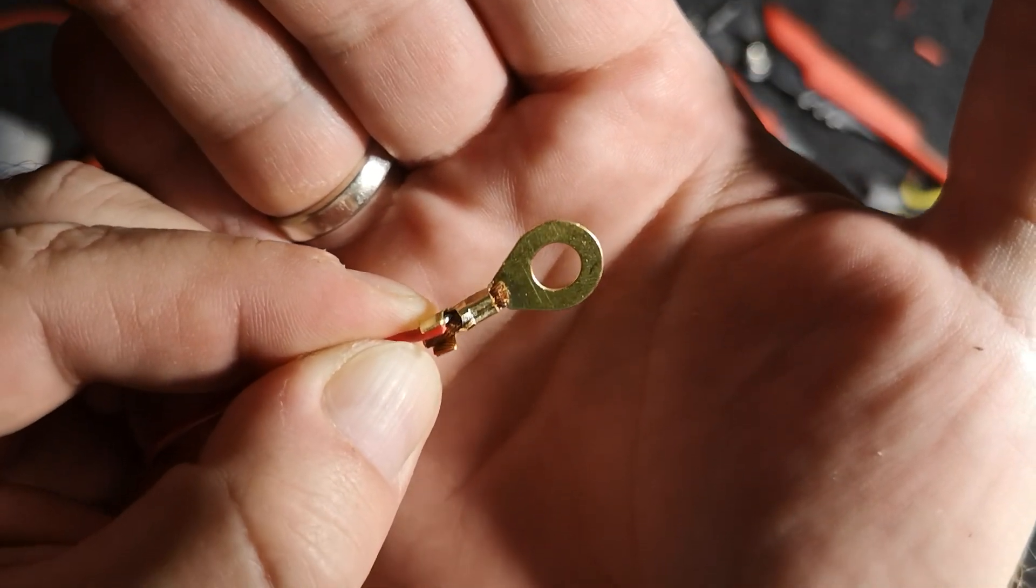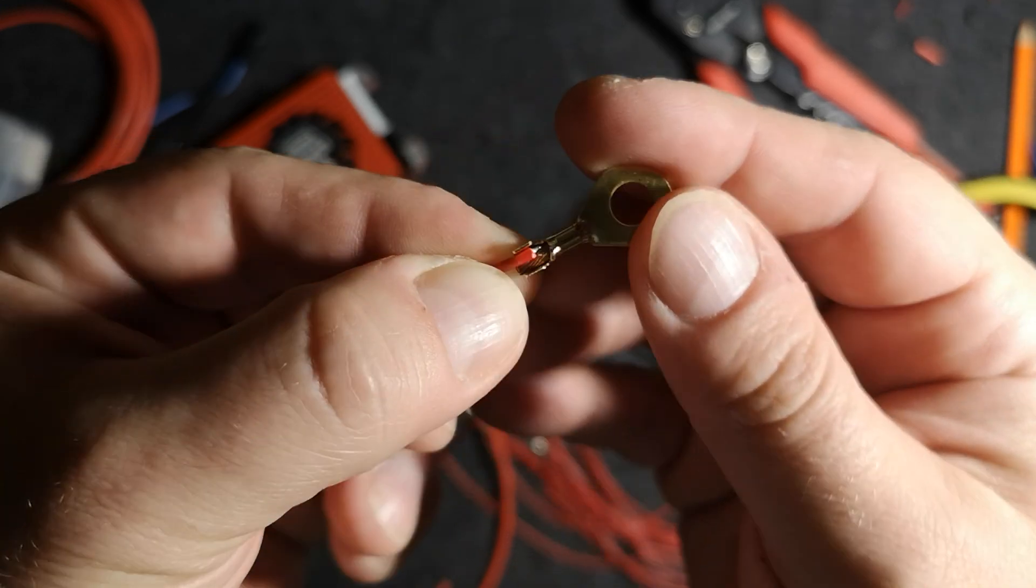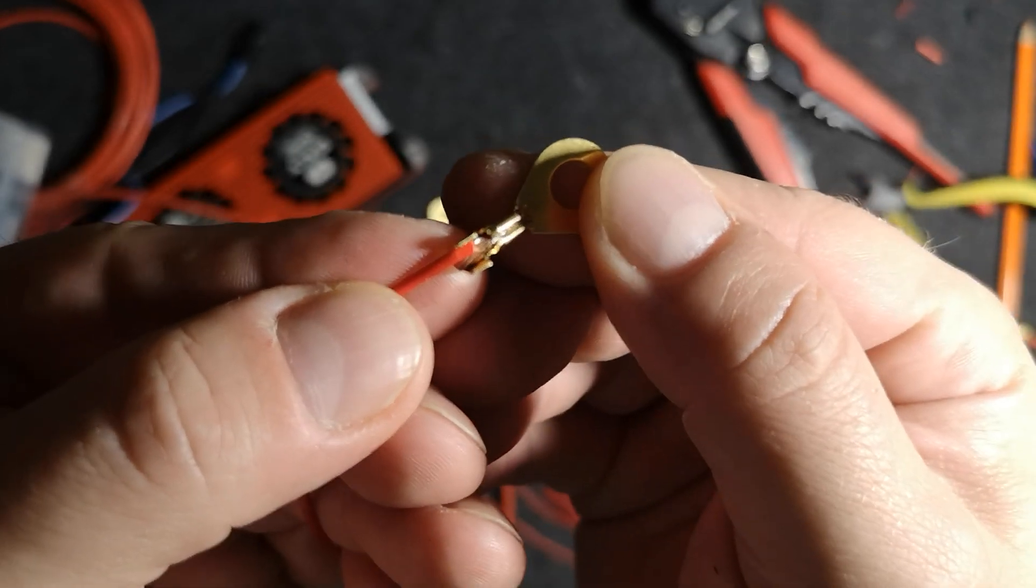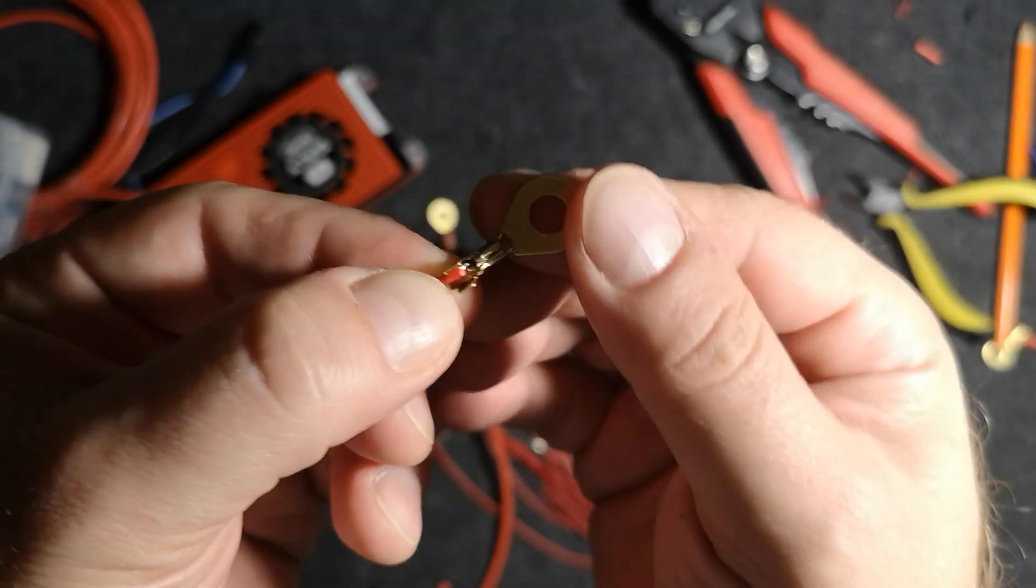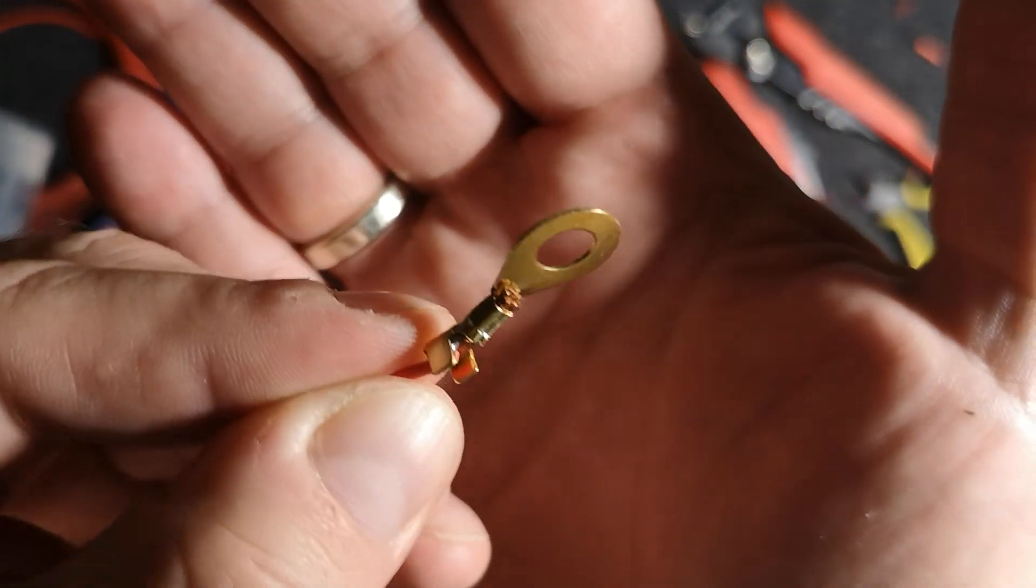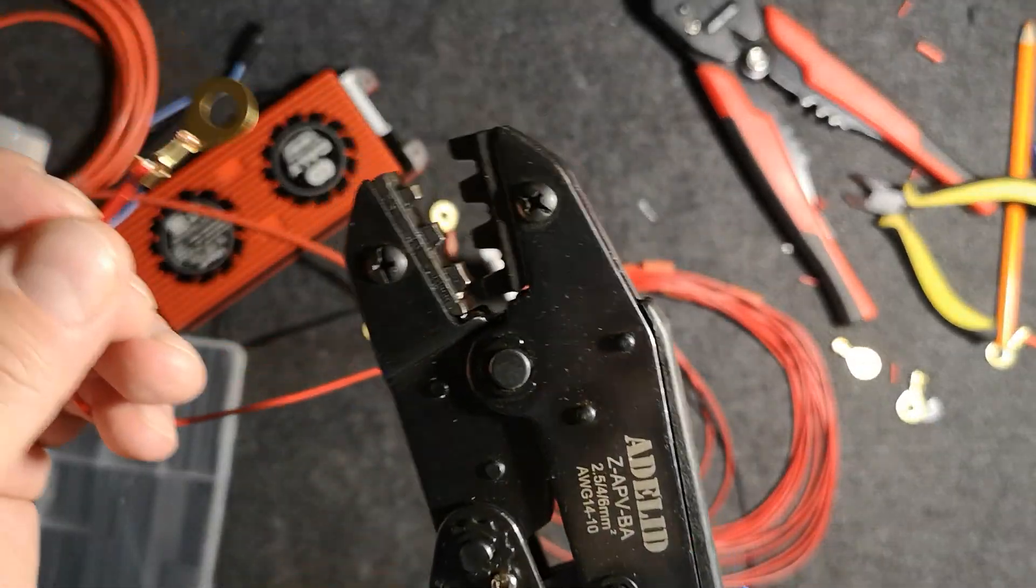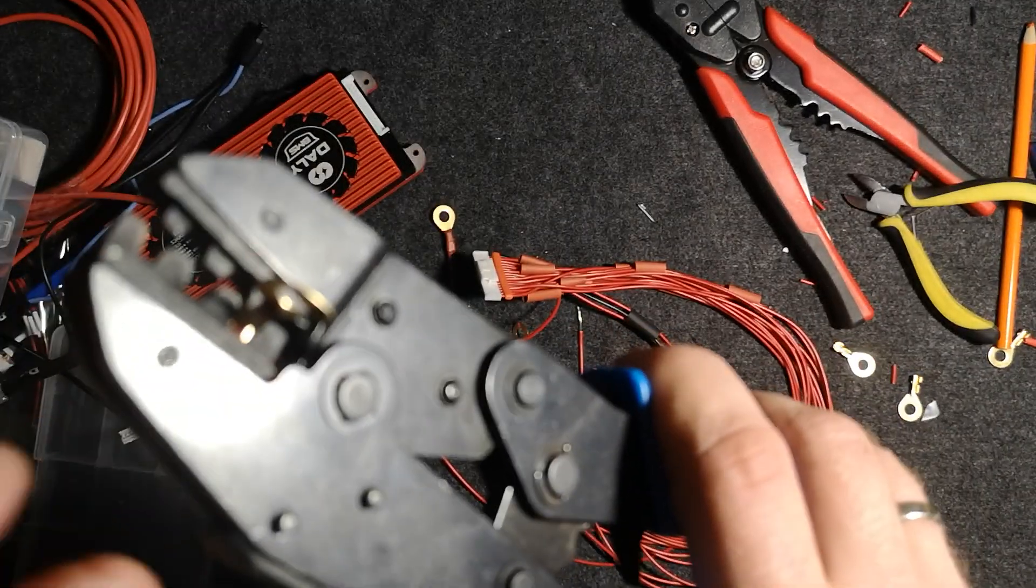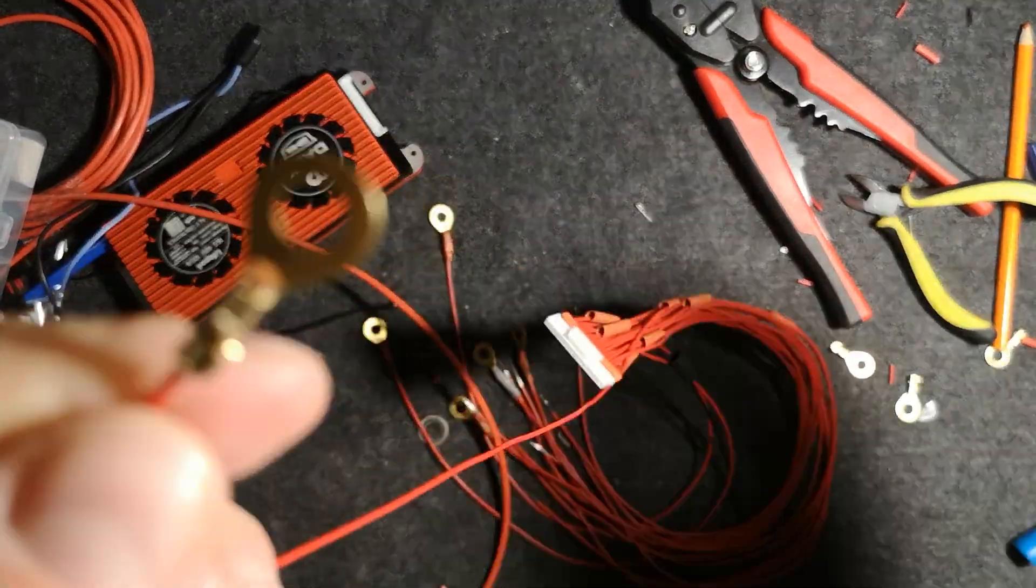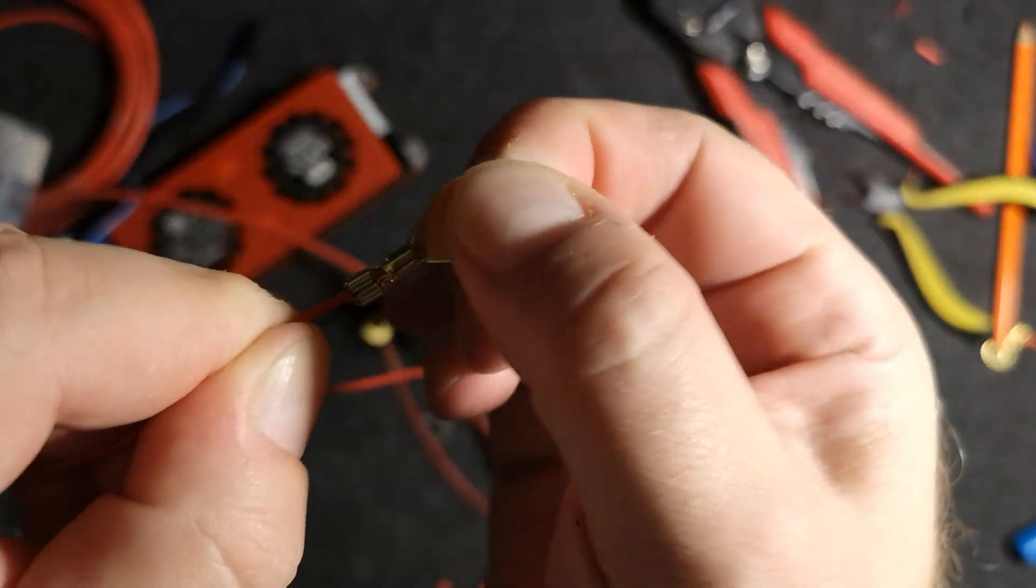The rest part is to crimp this insulation part, this one. I'm doing it the following way: I'm putting the red cable with insulation right or left and this naked copper to the opposite side as you can see. Okay, yes, it's in. I'm crimping it using 6.0, this last part. So in my case this is the last one. Make sure that you are not crimping the first part because we will be crimping only the last part. And now let's see: beautiful connection, secure, and nothing is going outside or inside.